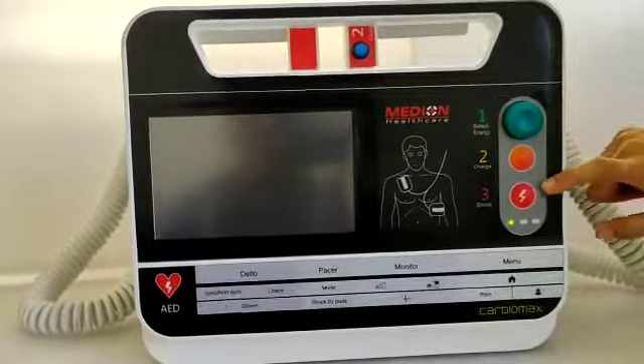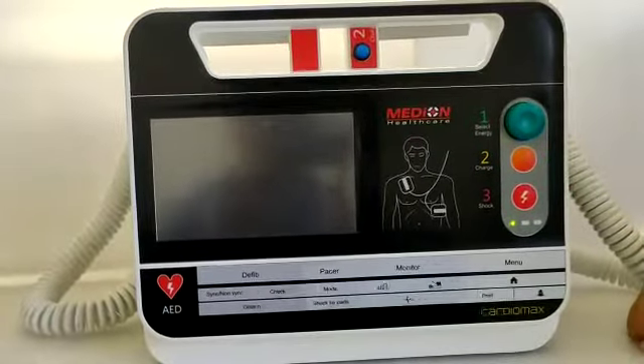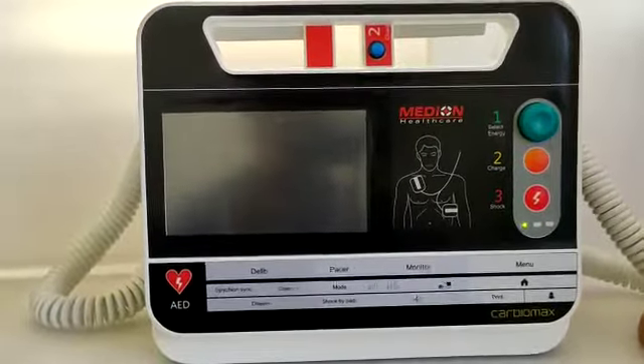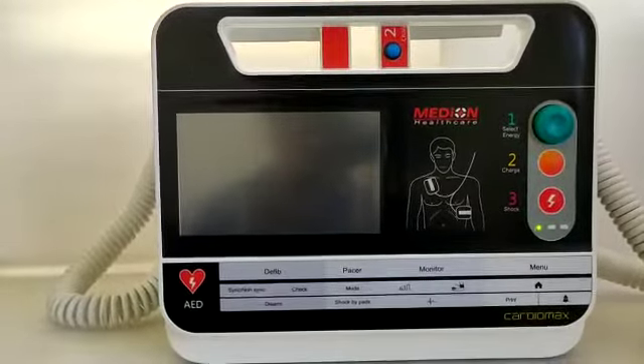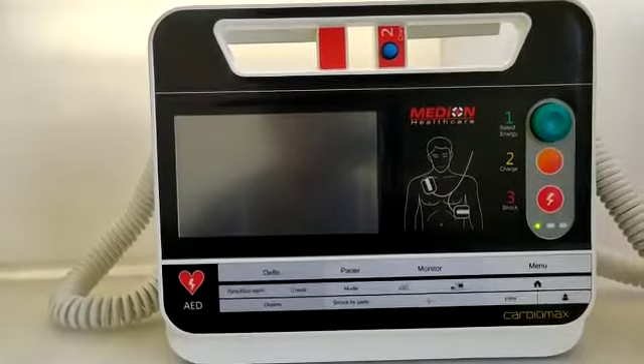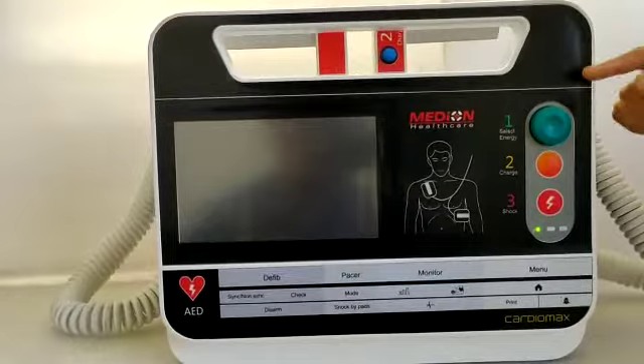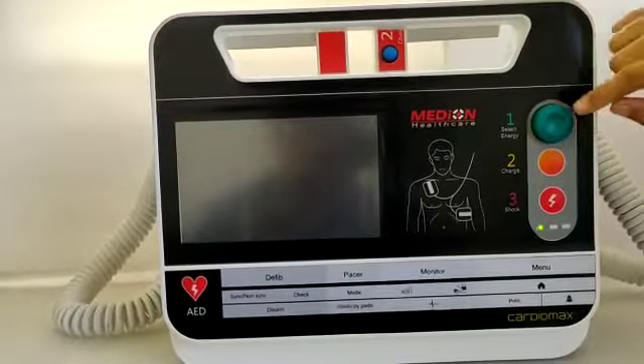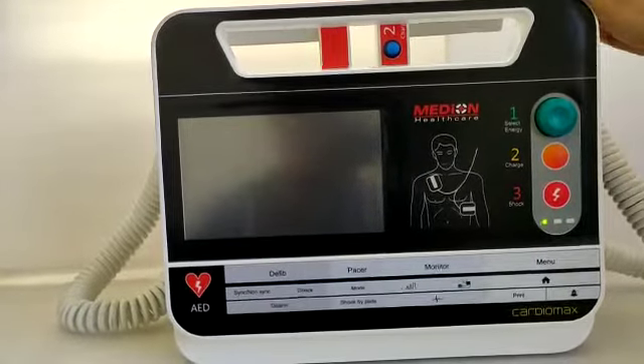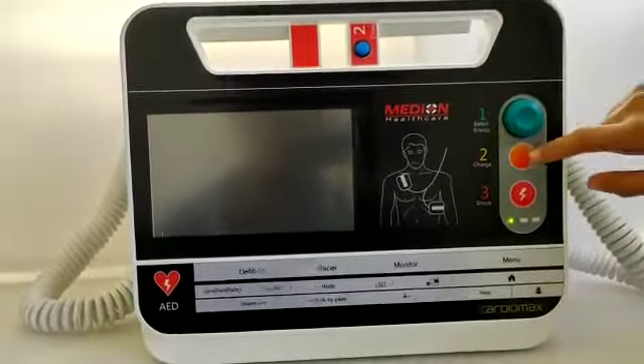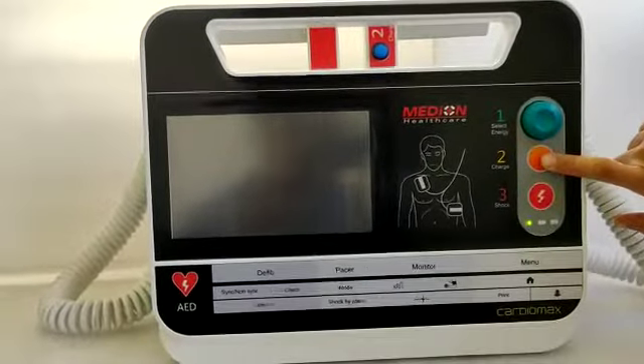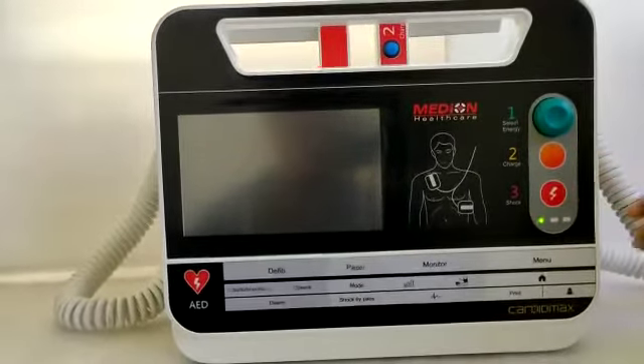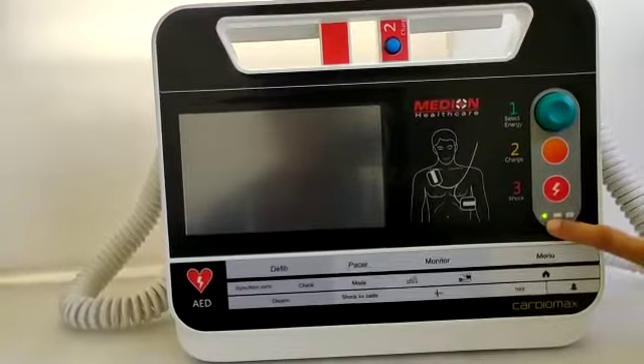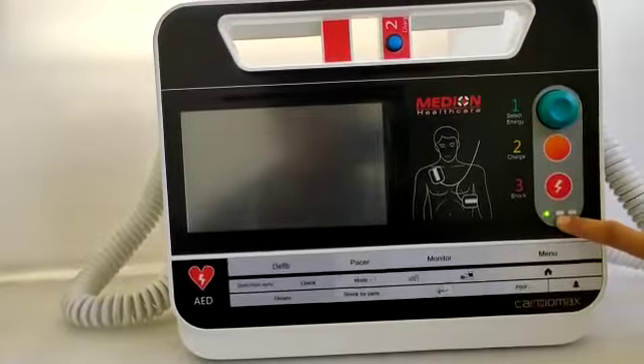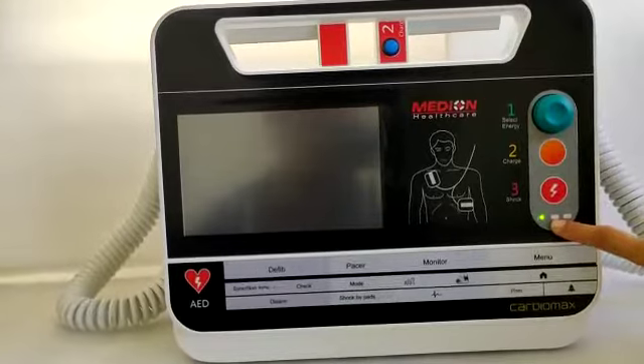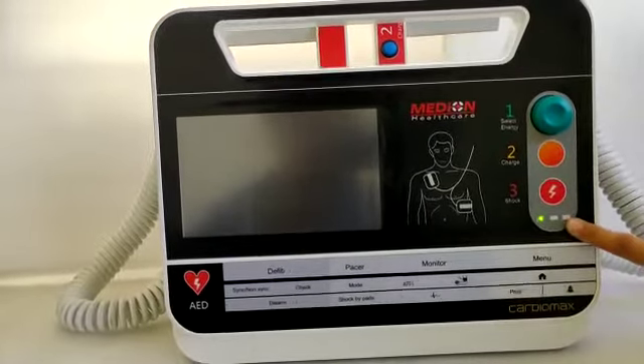Coming towards this, it is a rotary knob which is used to select energy levels as well as to slide to the other options, to increase or decrease the values and to save the changes. To save the changes, the user needs to press it. This is a charge button to charge the capacitor, and this is to deliver the shock. This is a mains connection indication. This is the indication that the defibrillator is working on battery, and this is for the battery load.